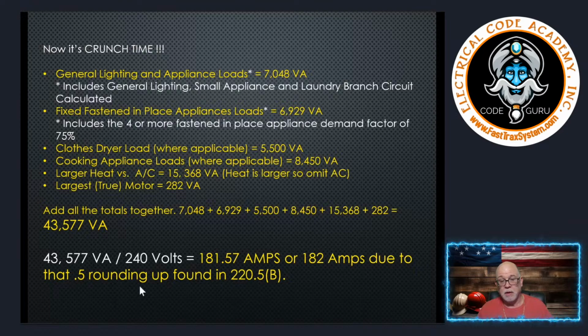Now, the first thing we need to do is size the overcurrent protective device. You and I both know that there is no overcurrent device that is 182 amps. Lucky for us, 240.4(B) of the NEC says that if it's not over 800 amps, and we're not supplying a branch circuit, which we're not, we're doing a load calc, and a breaker or fuse doesn't correspond, then we can go up to the next standard size. We still have to size a conductor to handle the load, which is 182, but we are allowed to go up to the next standard size.